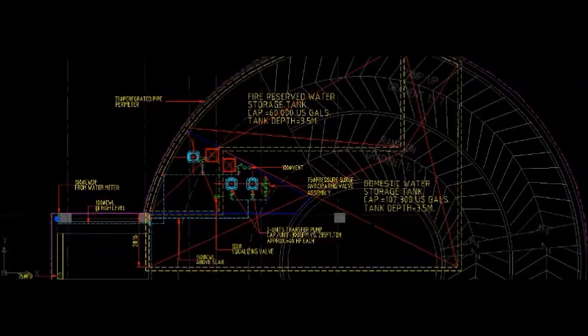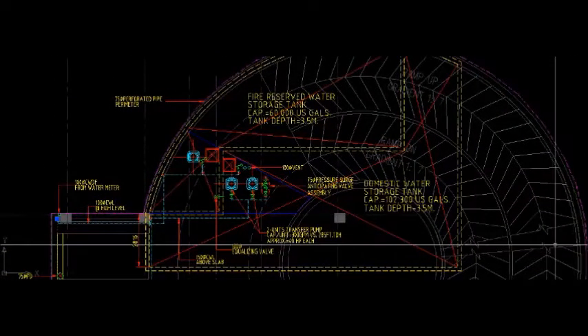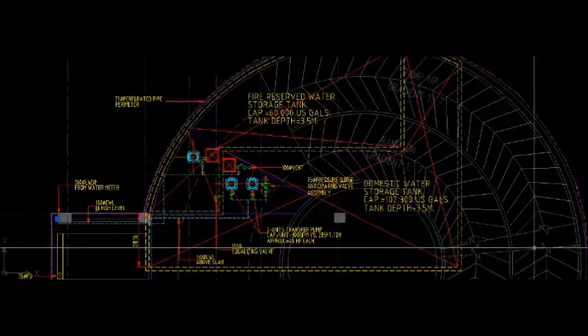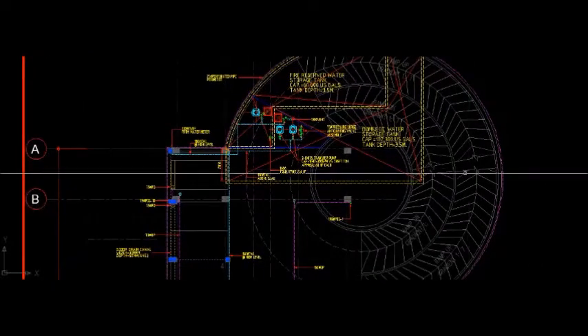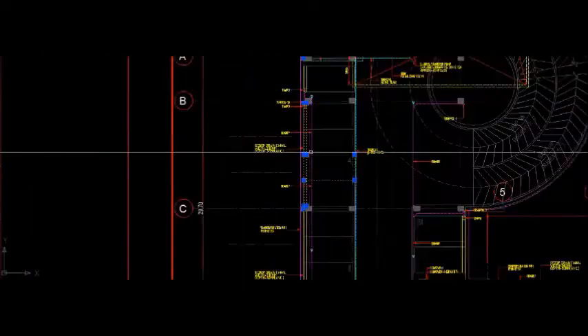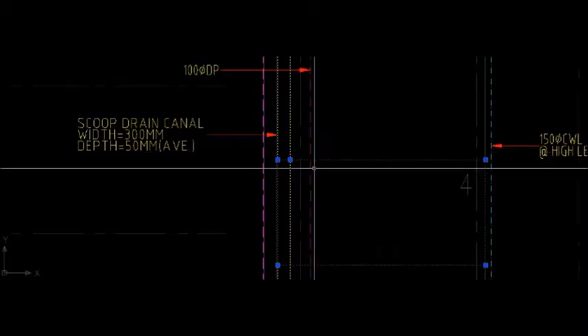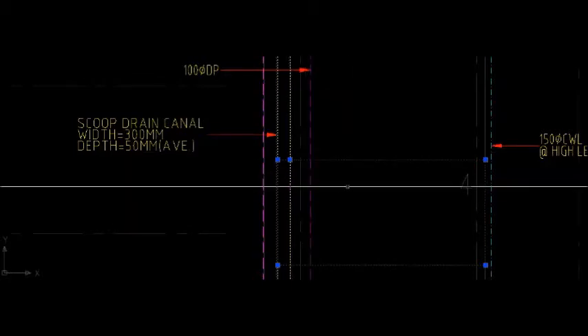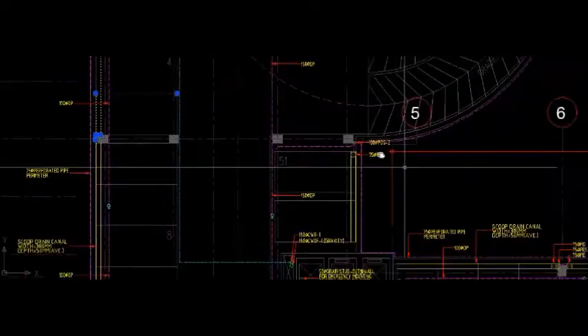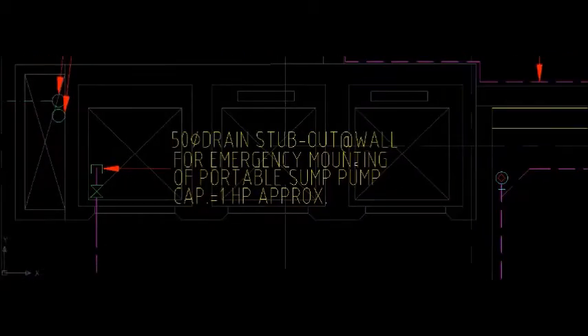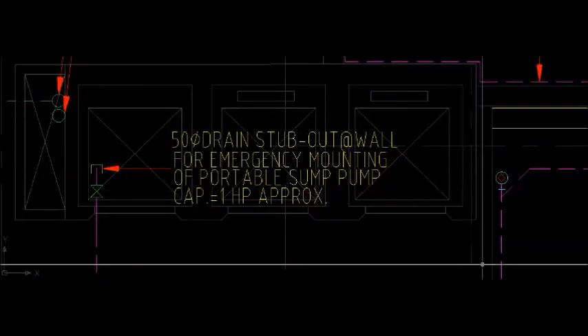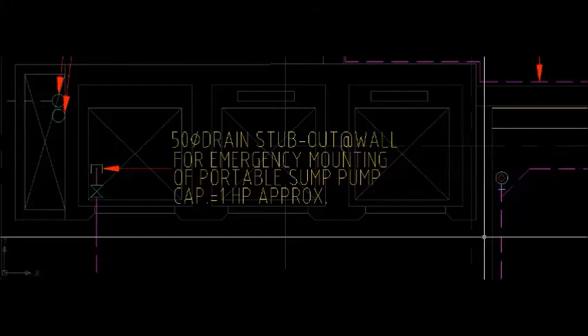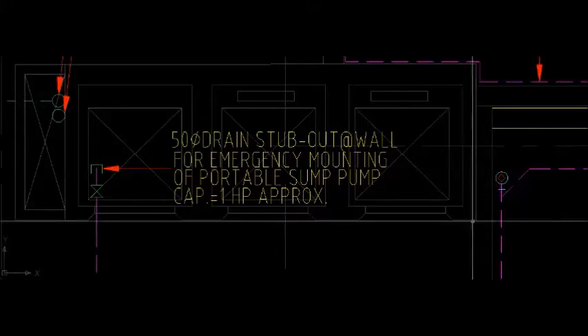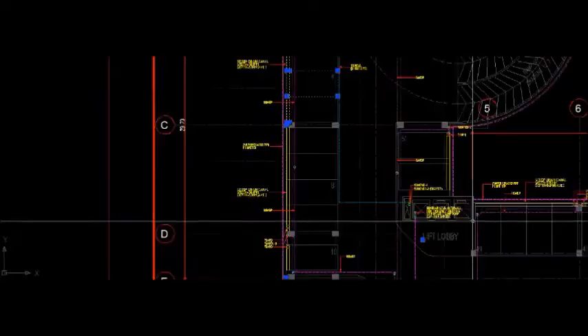As we can see, here is our fire reserve water storage tank with a capacity of 60,000 US gallons with a tank depth of 3.5 meters. And this is a scoop drain canal with a width of 300 millimeters and a depth of 50 millimeters average. And this is our 50 diameter drain stub-out at wall for emergency mounting of portable sump pump with a capacity of 1 HP approximately.